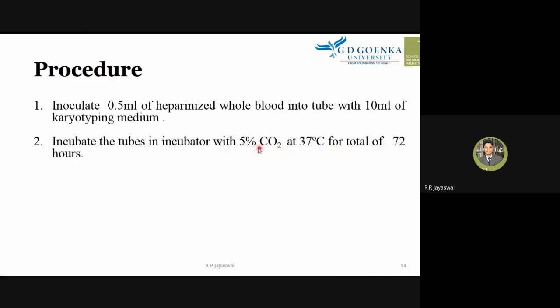This is the requirement: 5% carbon dioxide and temperature 37 degrees Celsius. So this is the requirement for the incubator. The incubator should be supplied with carbon dioxide and should be maintained at 37 degrees Celsius. So we can do the incubation for approximately 72 hours.